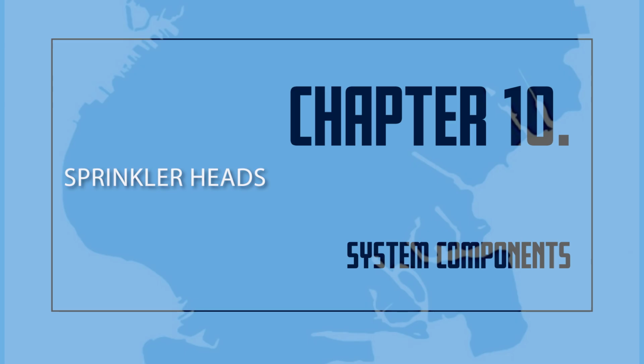Recalled sprinkler heads. A sprinkler head that has been recalled is called the cycling sprinkler. This sprinkler cycles water on and off depending on the temperature. When the disc reaches a temperature of 165 degrees Fahrenheit, the valve opens, permitting water to flow. When the disc temperature cools, the valve closes to shut off the water. These sprinklers and all other sprinklers listed for recall at www.cpsc.gov are subject to replacement.